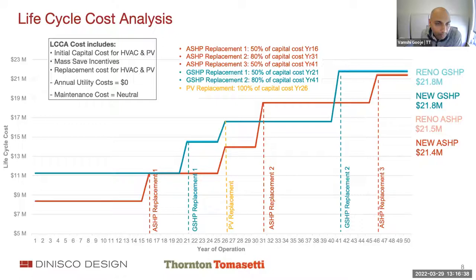As for the exact systems that will be replaced, Simon, if you're online, could you speak to that—what kind of systems would be replaced? For both air source and ground source, in the first life cycle, most likely the replacement is not wholesale, but more like compressor replacement and some fan and motor replacement. We estimated that to be about 50% of the capital cost. In the second round, most likely it would be almost a wholesale replacement, with the exception of some of the piping and ductwork distribution that's already in place.